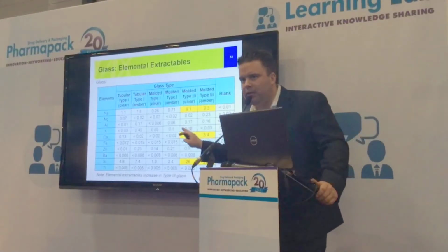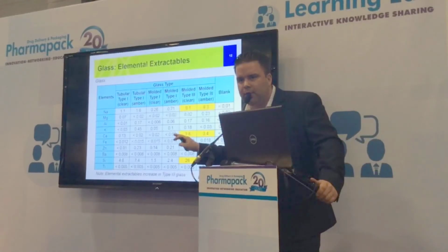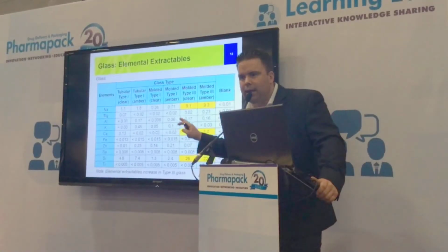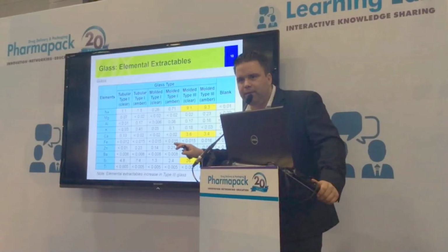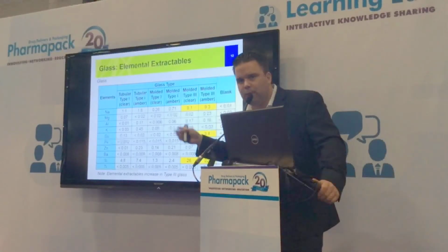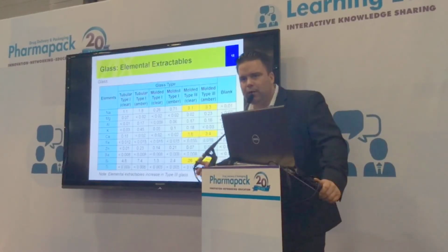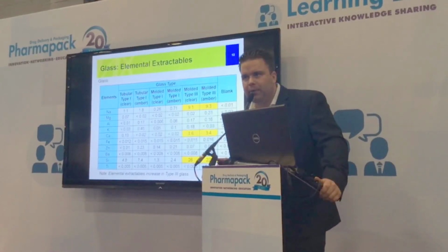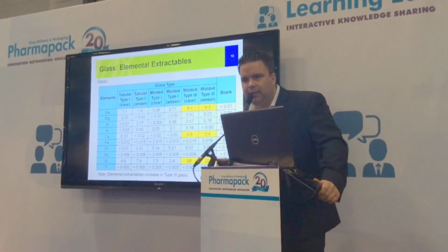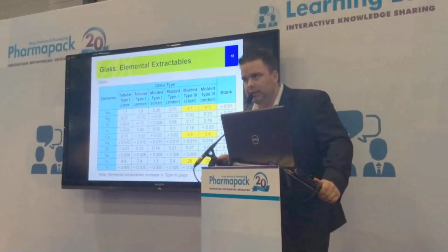Also, the background on this is that we put 20 milliliters of ultra pure water, pH of 7, inside 30 ml vials. We autoclaved it for 60 minutes, which is well over the hydrolytic test standards for EP Chapter 3.2.1 and USP Chapter 660. So we autoclaved it 60 minutes at 121 degrees Celsius.